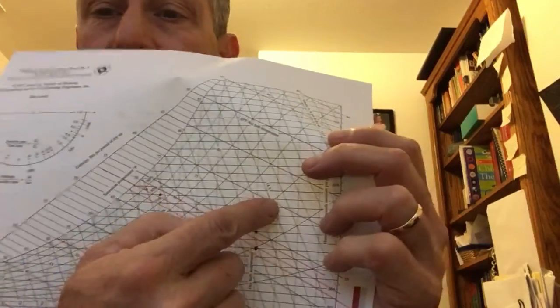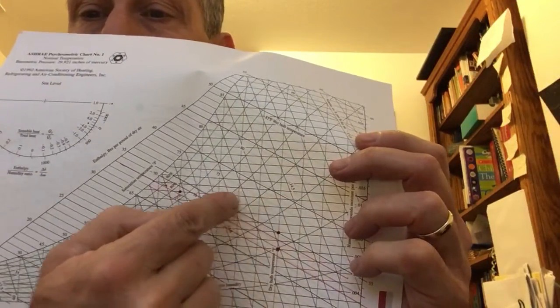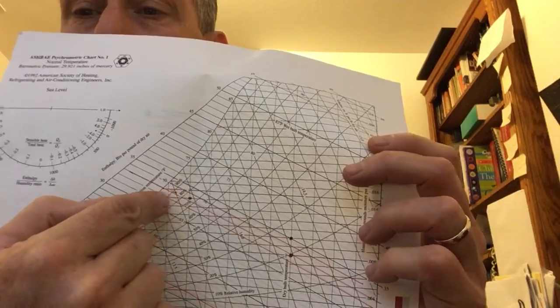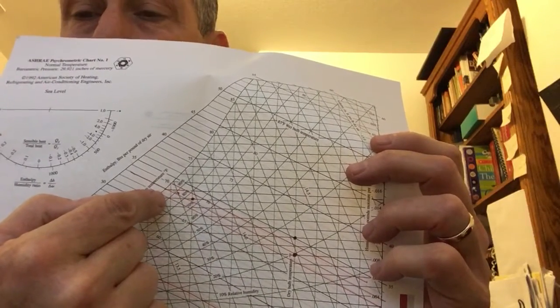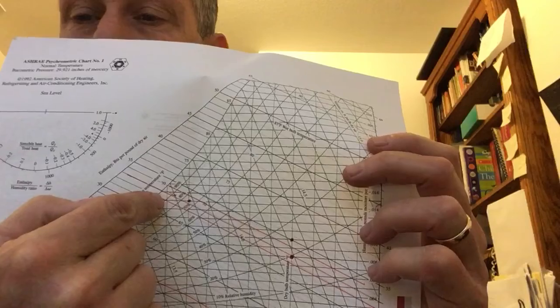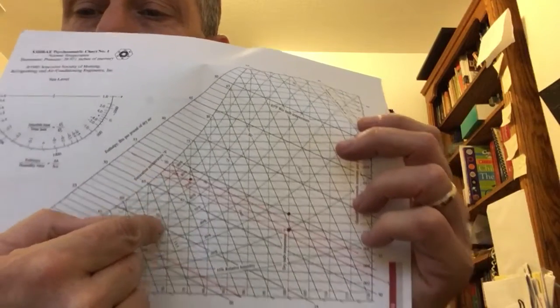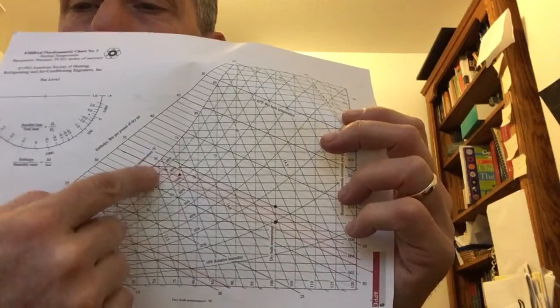So, to repeat again, the last process. If you have some air and you want to figure out its dew point, plot that air on the psych chart, and then just draw a horizontal line until you hit the saturation curve. That's where dew begins, and you're going to read that temperature. One way you can do it is go right down there and get the dry bulb temperature.